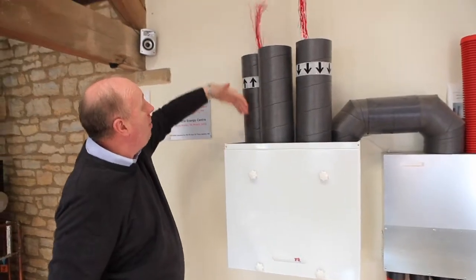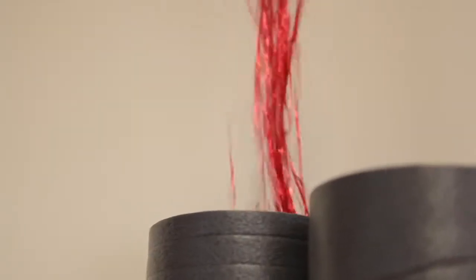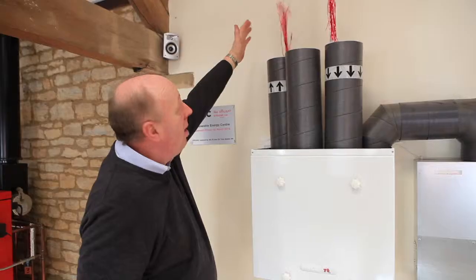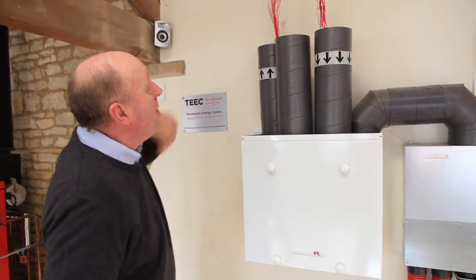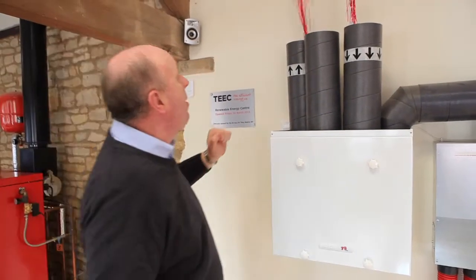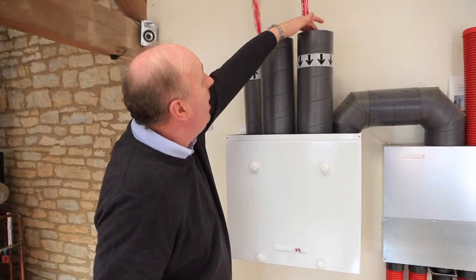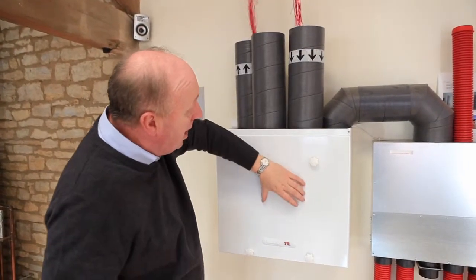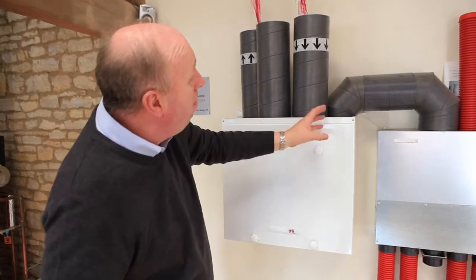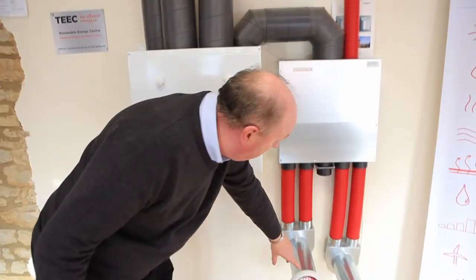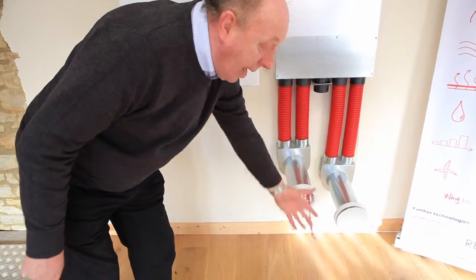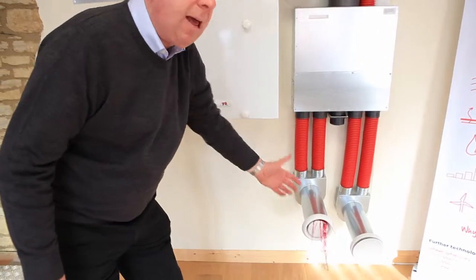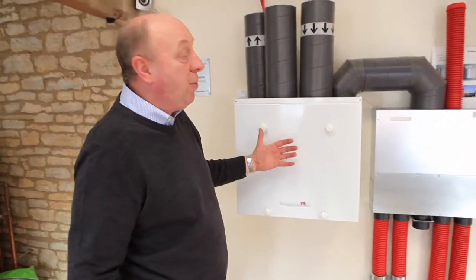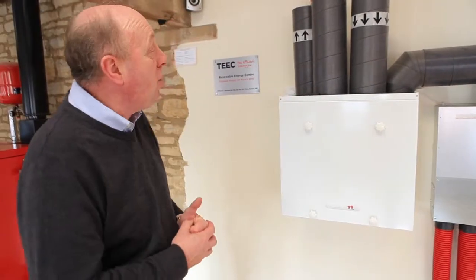You can see these streamers. That's then going outside. That's the waste part of the air with all the parts that we've taken out of those wet areas. And then we're bringing our cold air back in through this duct. It's going over this heat exchanger, and then it's coming back through into our plenum system, and it's distributed that air back into the building, and within that air is the recovered warmth that we've taken from the extracted air.